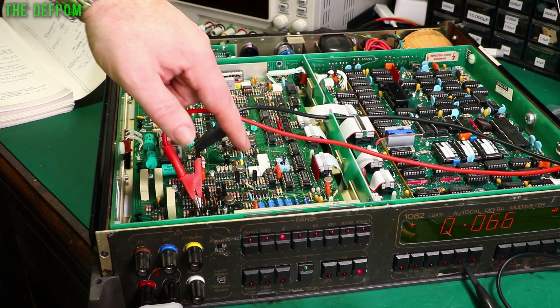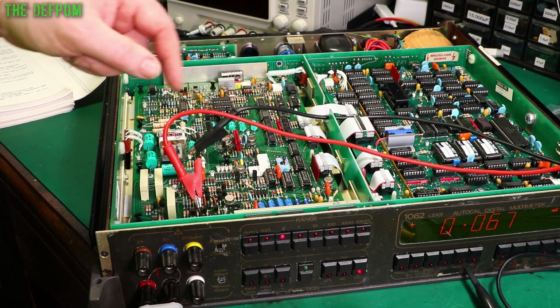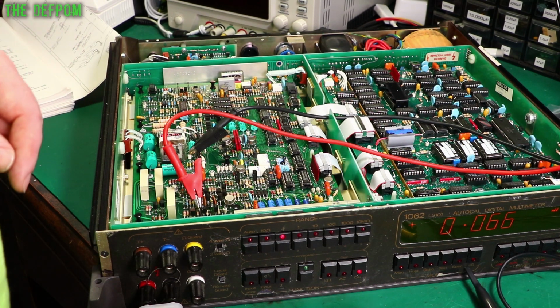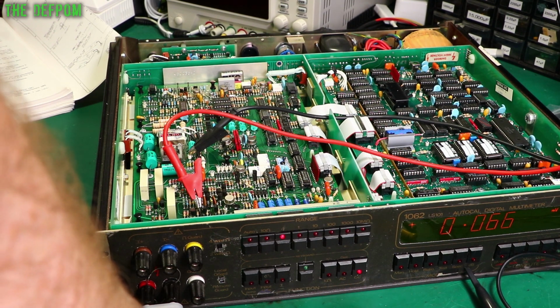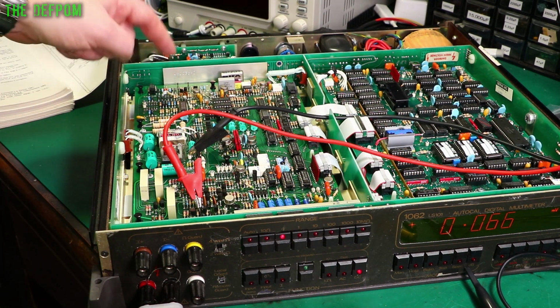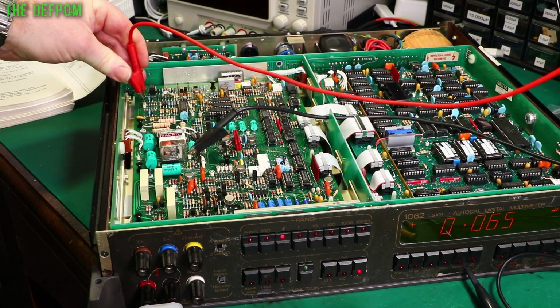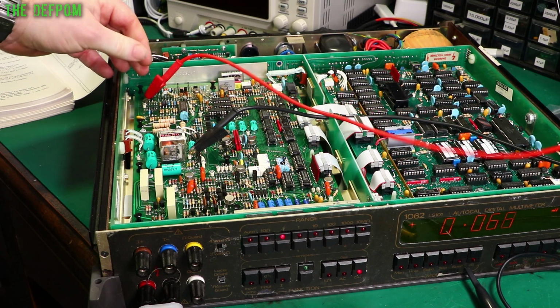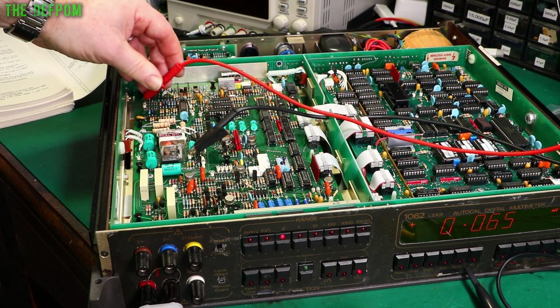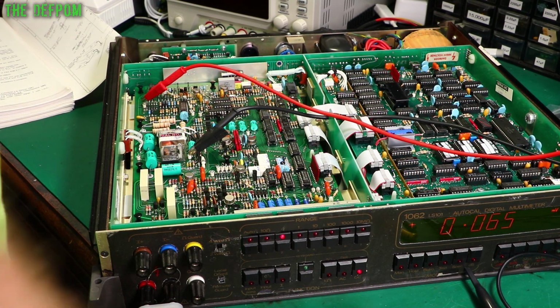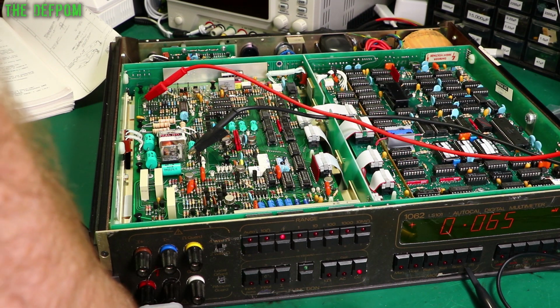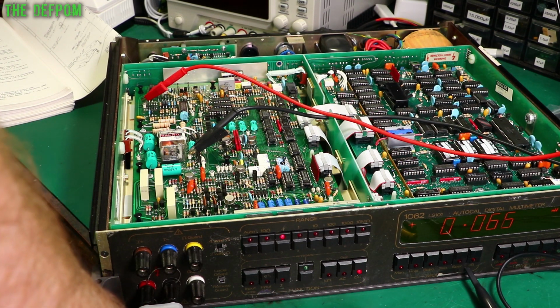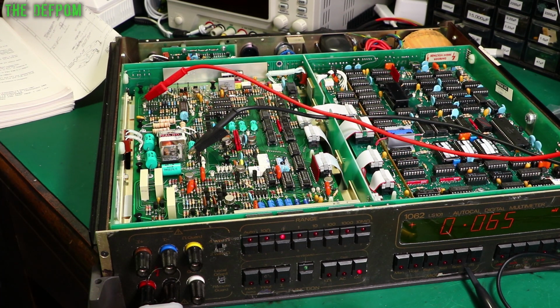So I'm not going to adjust that, which is for this adjustment over here, R151 I think it was. So no need to do that, I'm skipping that section. The next section is about verification of the reference, which is over here. So let's unplug this one from here, go to TP7, which is here, and they should read about 6.42 volts plus or minus 0.03 volts. So I can go from 6.39 up to 6.45 volts at that test point.